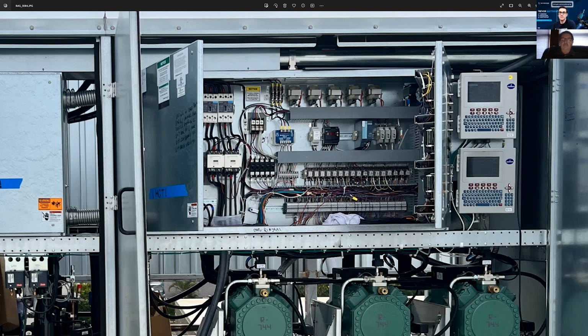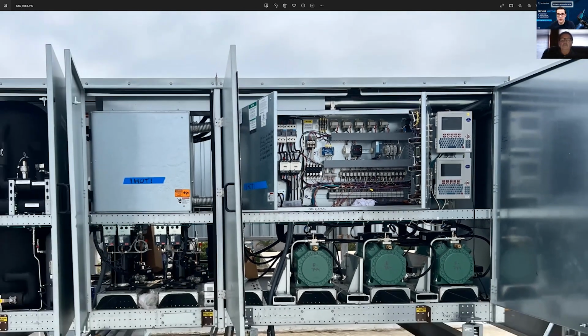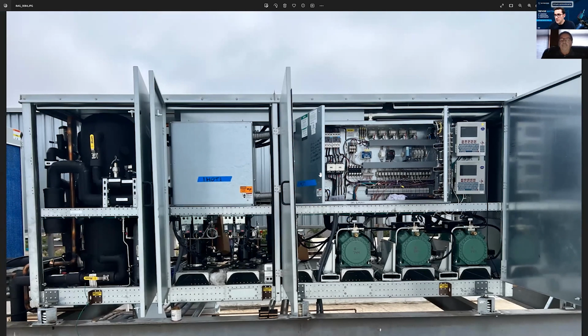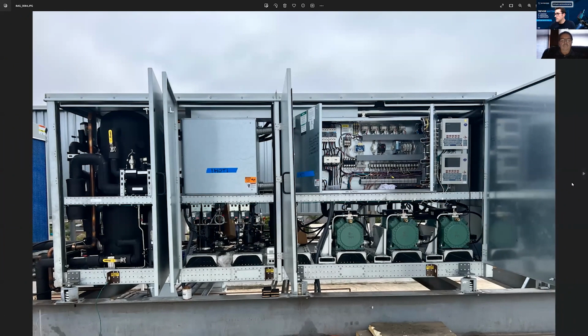That's correct. Now, if you do have an issue with your filter, just pull the wires off the bottom of the filter and connect them directly to the bottom of the 326A. Order a new filter. Yeah, because it could be the filter. You want to make sure that you're not replacing components. I've seen it and heard it before where they're changing a valve and it's a transducer that's the issue, not the valve. Things like that.